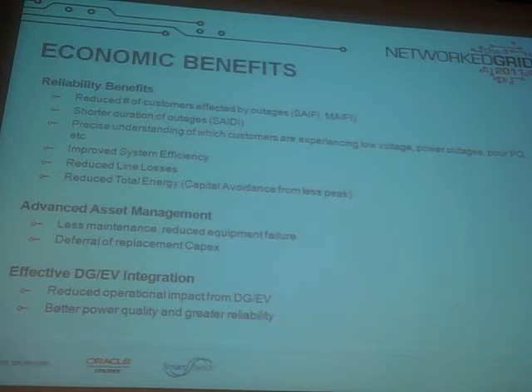I was talking to a utility at Northeast Utilities last week, and they said our line losses are actually quite low, so reliability was really how we made the case to our commission. Fifteen minutes later I was talking to APS, Arizona Public Service, and they said we had 7% line losses, and after putting in volt-var we dropped that to 3%. That's a pretty substantial example of the savings you can get from volt-var.